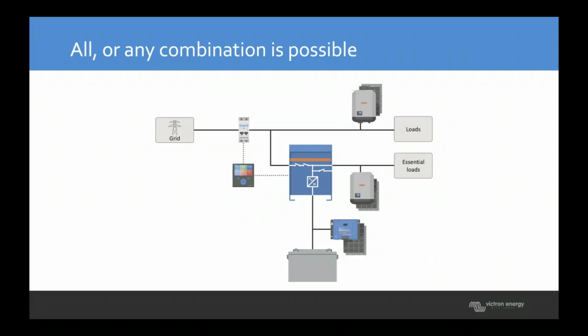It's also possible to have all combinations of the above in a grid-connected system. You can have AC PV connected on the input, and this is unlimited or limited to your circuits and your grid supplier. You can have AC PV on the output, and this is limited to the size of the Multi-Plus in the event of an outage. And you can have DC PV connected directly to the DC bus before the Multi-Plus. And this is also relatively unlimited, relative to the size of the battery. You can't have too big a PV array on the battery if the battery is very small.